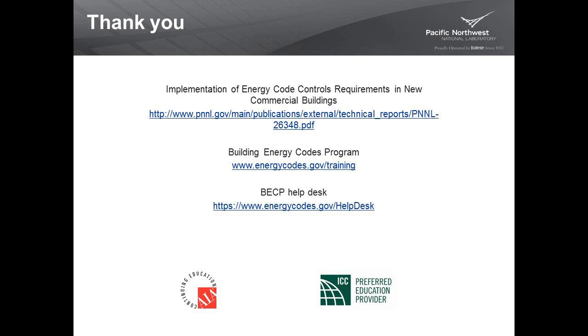The point that I was making is that if these specific controls, whether it's thermostat deadband, simultaneous heating and cooling limitations, occupancy sensor control, are not configured correctly, but they're capable, in other words, all the equipment's there and they've got set points and settings that just need to be adjusted to configure them, while it's not always as simple as just changing a number somewhere, sometimes it takes some expertise, it is much lower cost than if these controls were not capable at all in the first place, and you had to buy material or equipment in order to get that done. So that's why I say it's low or no cost.